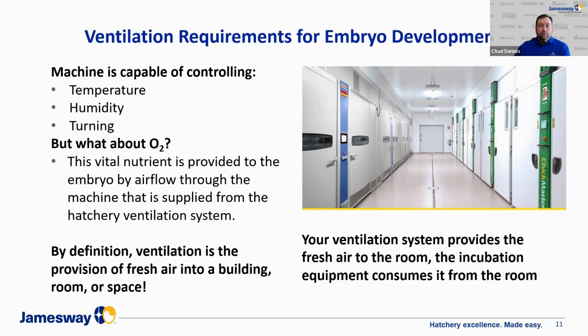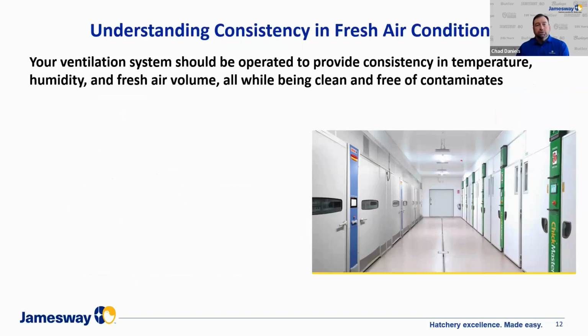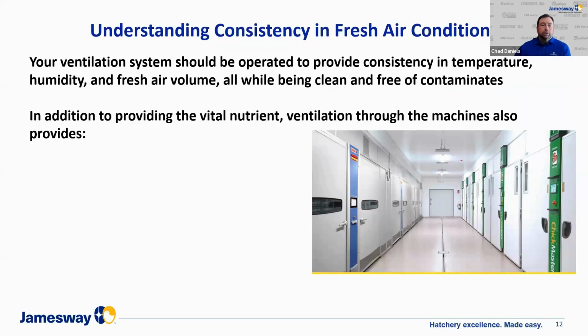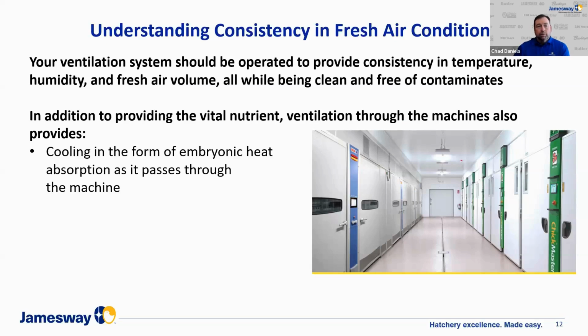A different way to look at that sometimes is that our ventilation system provides the fresh air to the room. The incubation equipment consumes it from the room. Oftentimes we don't really look at it from that perspective, but that's what our incubation equipment is doing. It's consuming the fresh air from the room. So your ventilation system should be operated to provide consistency in temperature, humidity, and fresh air volume, all while being clean and free of contaminants. So in addition to providing the vital nutrient, ventilation through the machine also provides, and this is the first piece, cooling in the form of embryonic heat absorption as it passes through the machine.